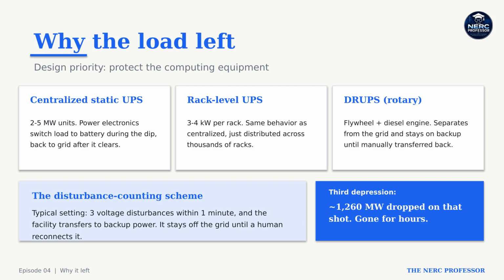A data center has one design priority: protect the computing equipment. Voltage trouble damages servers, so every facility sits behind an uninterruptible power supply. Some use big centralized UPS units, 2 to 5 megawatts each. Some use small rack-level units. Some use rotary systems, flywheels coupled to diesel engines that physically separate from the grid and do not come back until someone reconnects them manually. Many facilities run a protection scheme that counts voltage disturbances. The typical setting: 3 disturbances within 1 minute, and the facility transfers to backup power and stays there until a human transfers it back. Now replay the event.